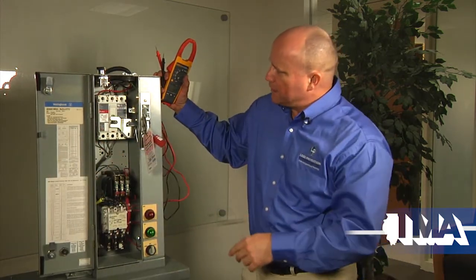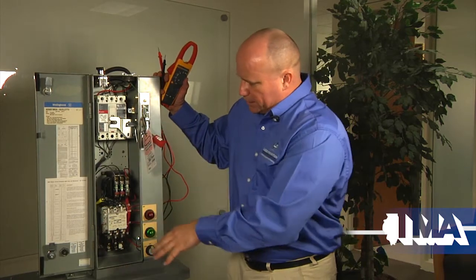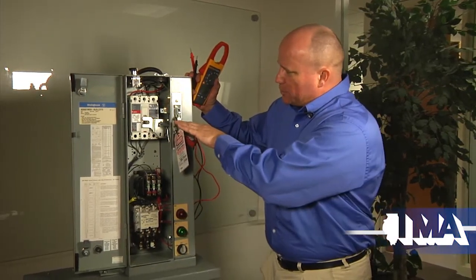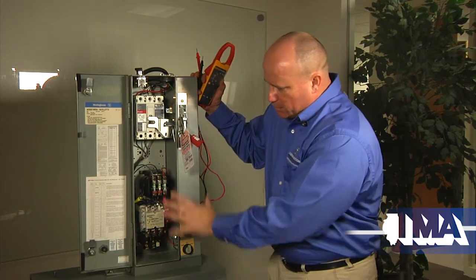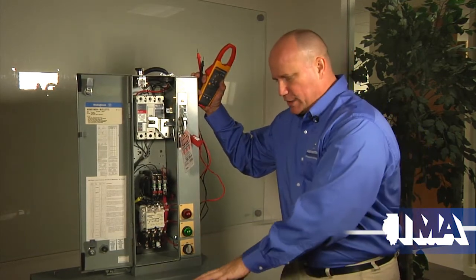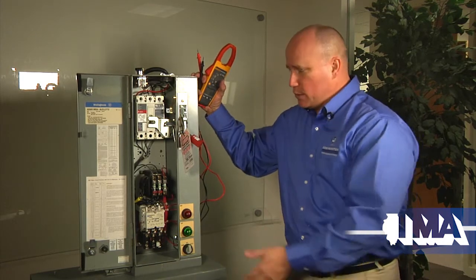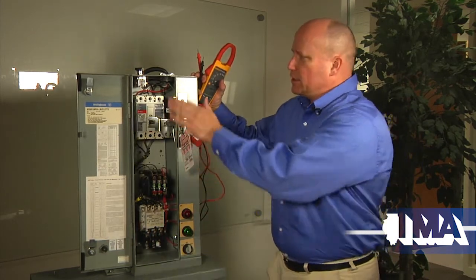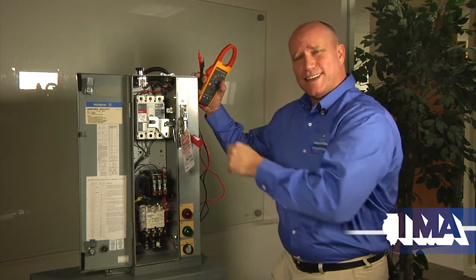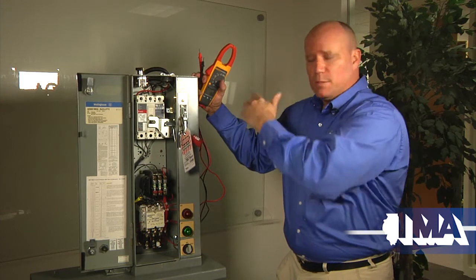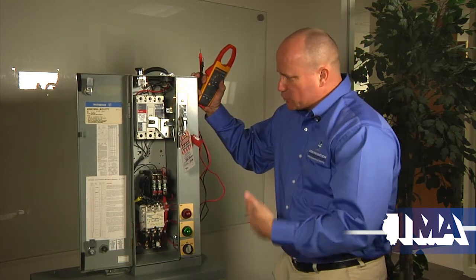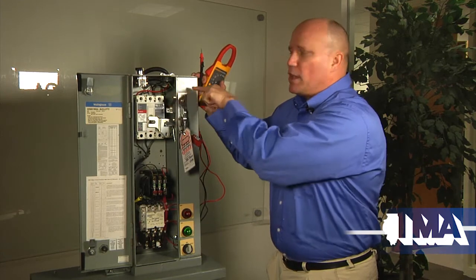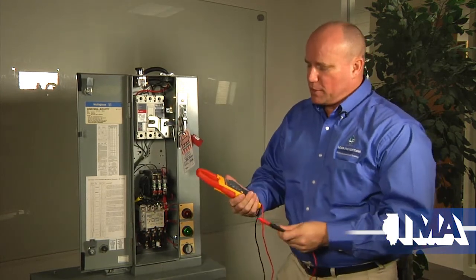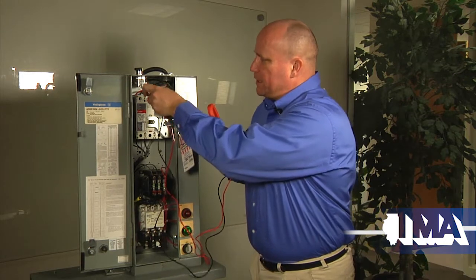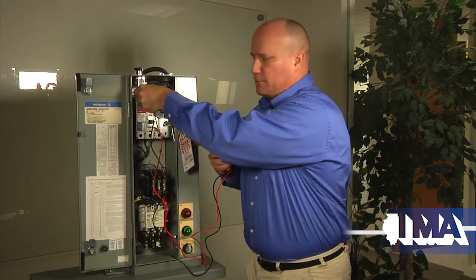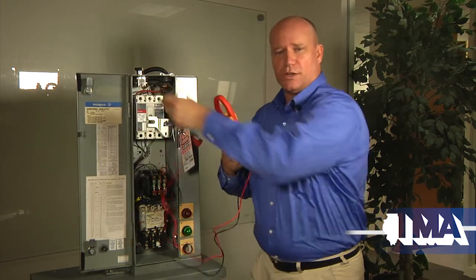The first thing is a live test. Now since this is my isolation point, when I'm doing a lockout tagout, I can determine that, not have to go upstream if I'm working somewhere outside of this controller. Somewhere down, like for example, motor replacement, which is outside the controller. If I'm working anywhere in here, since there's not a protective guard there and there's a possibility of contact, my isolation would be upstream. But since my work scope is outside this controller, I can use this as my isolation point, and I know I have a known live source here. Okay, so all I have to do is verify that my meter indicates the way I expected it to. I should get a reading, in this case 208 volts.